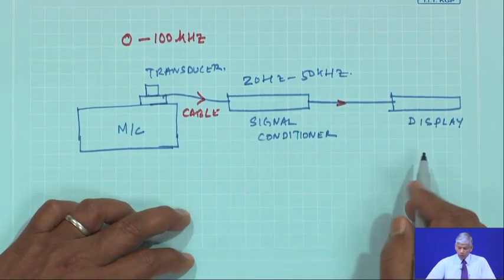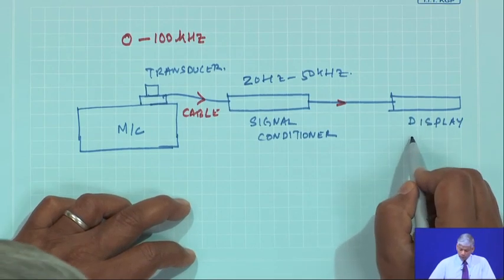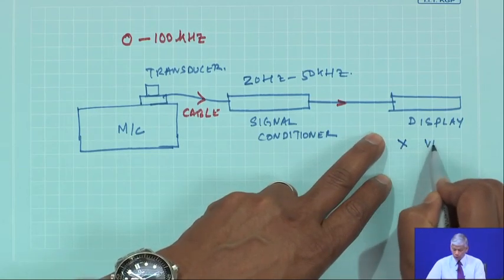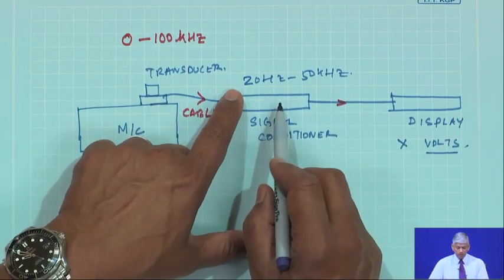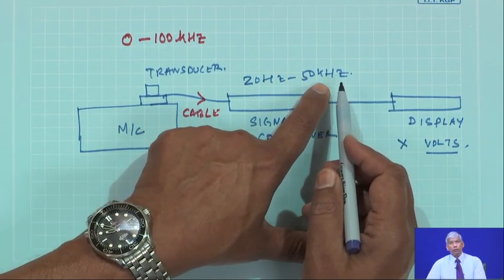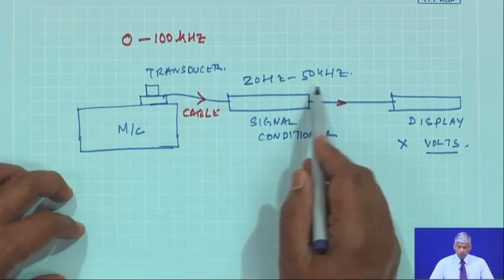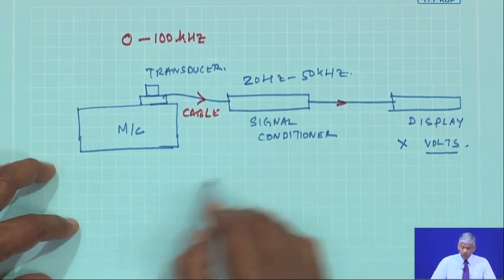Obviously you would be asking: when I see a value on the display, I cannot say that whatever value I get in x volts is from 0 to 100 kHz, because the signal conditioner is not going to respond to anything below 20 Hz or above 50 kHz. You may be having values from 50 kHz to 100 kHz, but those would not get propagated because the signal conditioner has a limitation.